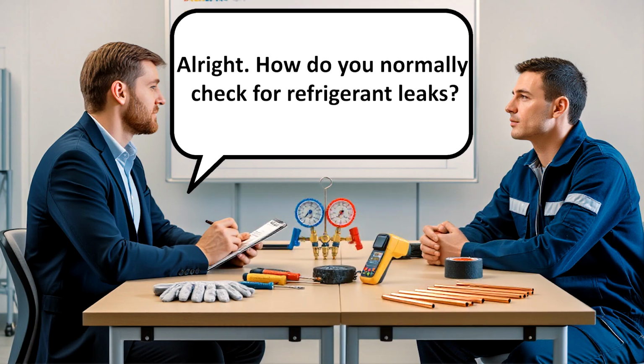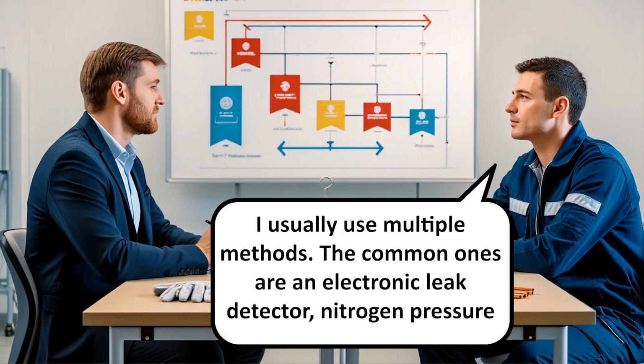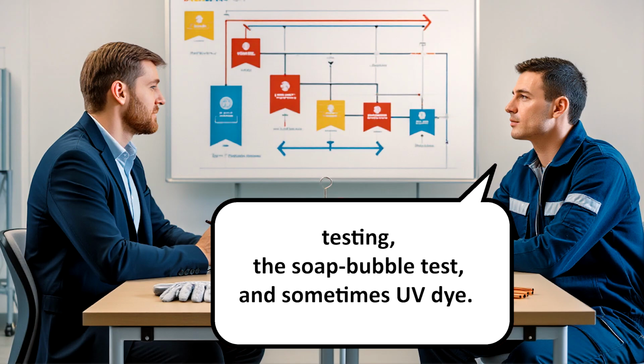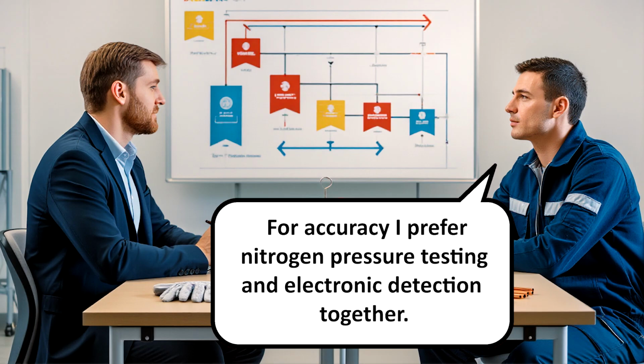All right. How do you normally check for refrigerant leaks? I usually use multiple methods. The common ones are an electronic leak detector, nitrogen pressure testing, the soap bubble test, and sometimes UV dye. For accuracy, I prefer nitrogen pressure testing and electronic detection together.